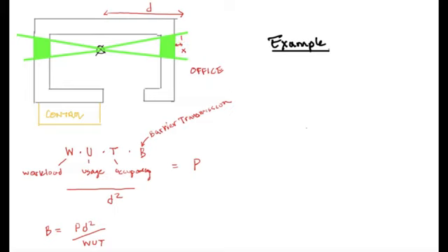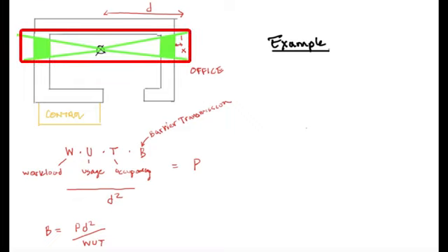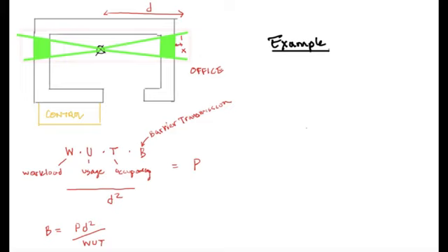So first of all, let me explain the geometry here. I've drawn out these little green areas. What this is indicating is the fact that the linear accelerator can point to either of these walls as it rotates around. It could also point down towards the floor or up towards the ceiling. When it points towards the wall, towards the office, it's going to irradiate this green shaded area here. So this is the area you would have to shield.